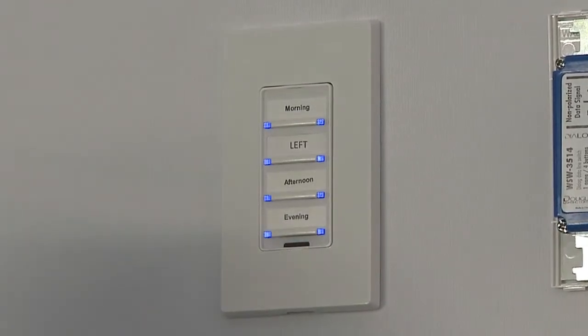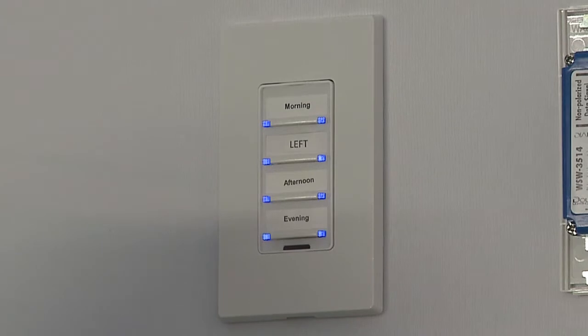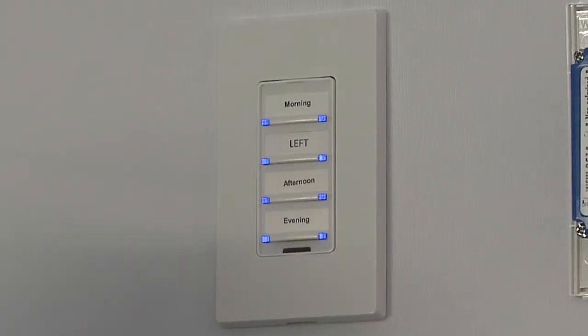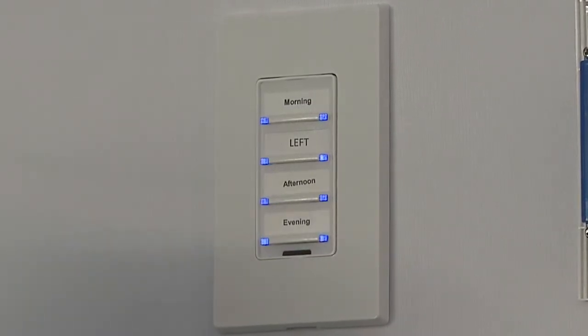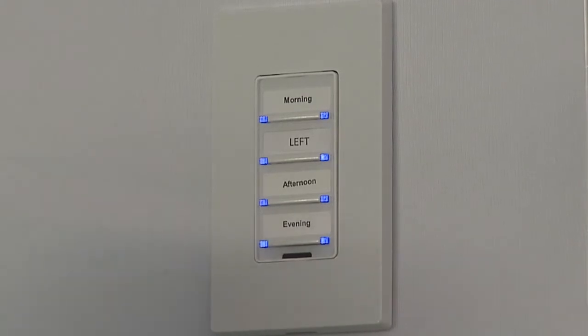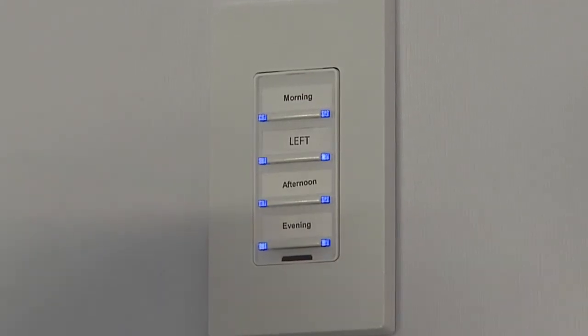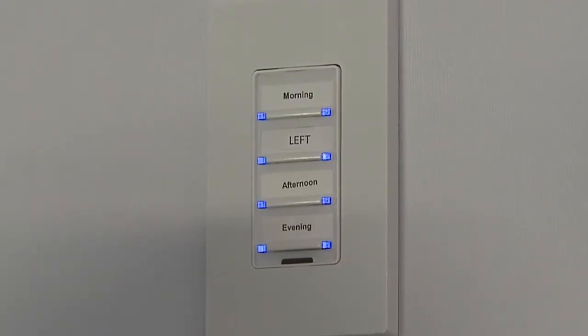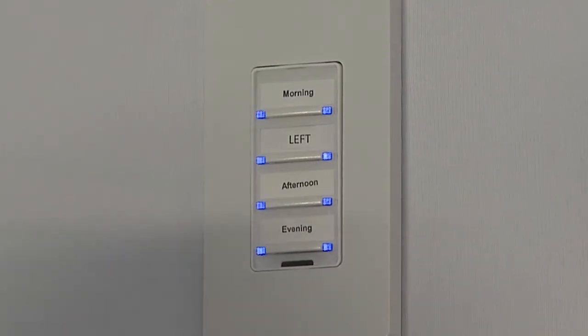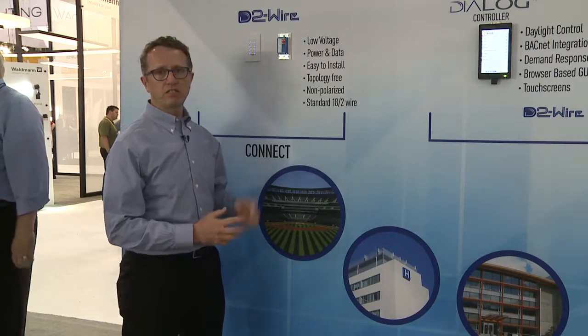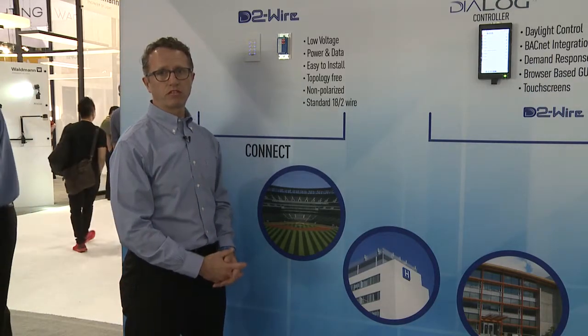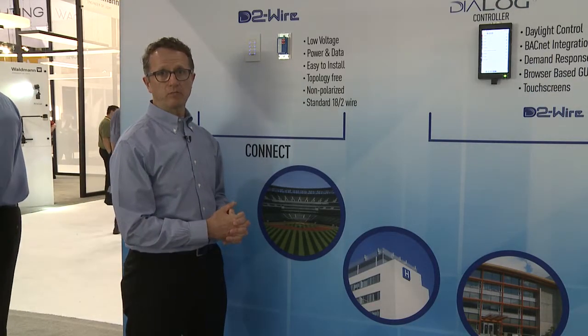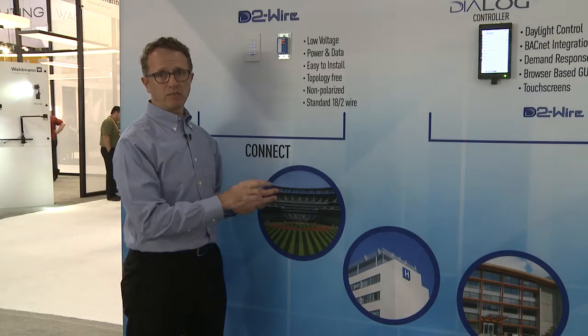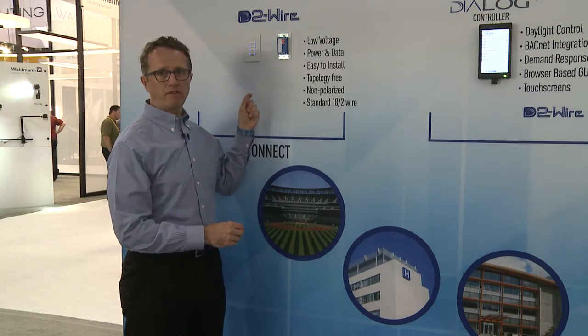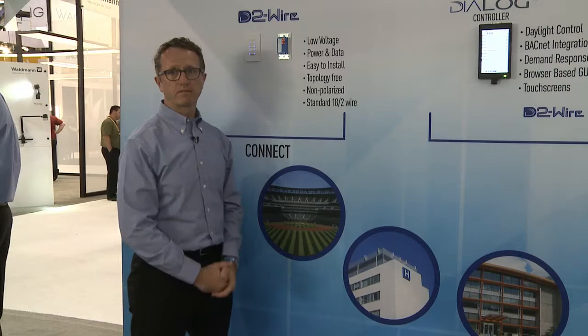This one's set up for possibly a classroom or office type application where you have a morning setting, a lunch or afternoon setting, and an evening setting, so the light is set in a particular way for each time of day. You could also set those up to just be straight application or presentation mode. Each device in the Dialog network is controlled through that 2-wire standardized bus, which runs as a backbone, and then you just do T-drops off each device to connect into the network.